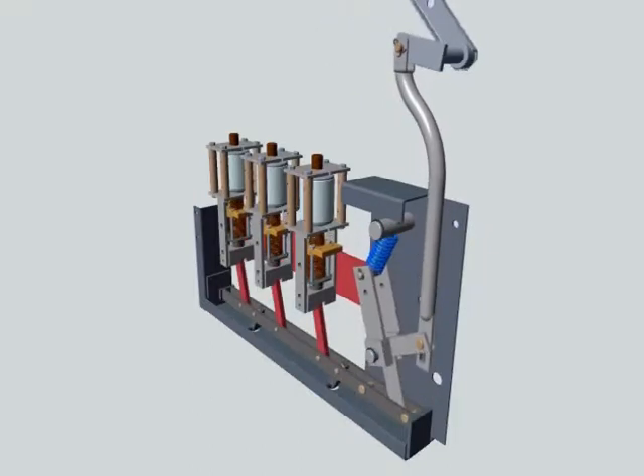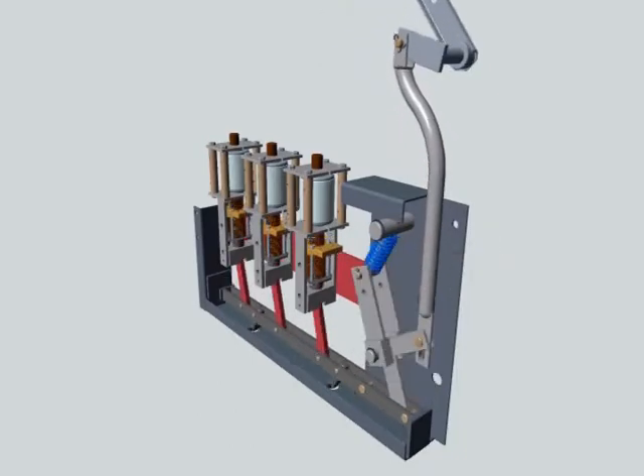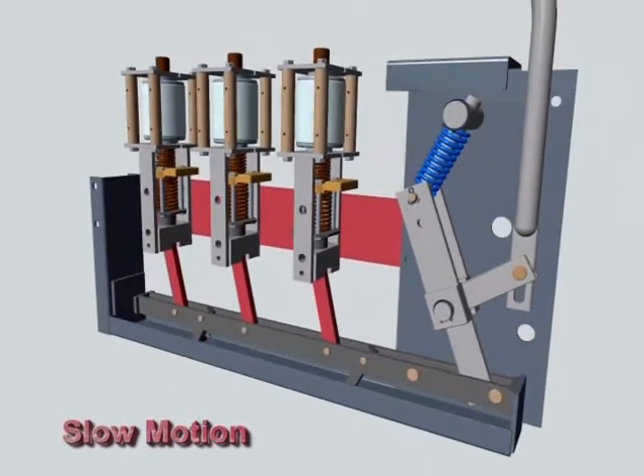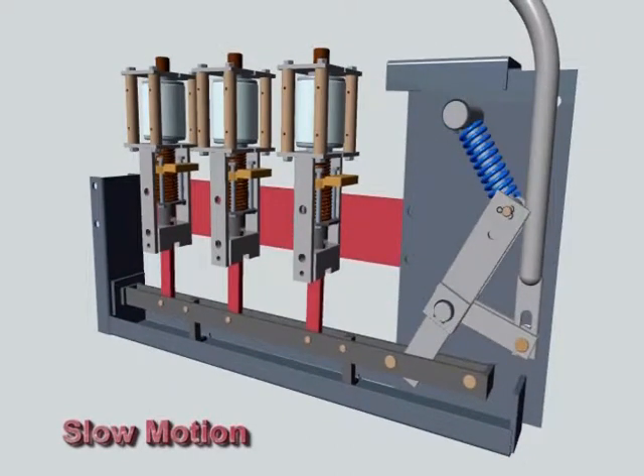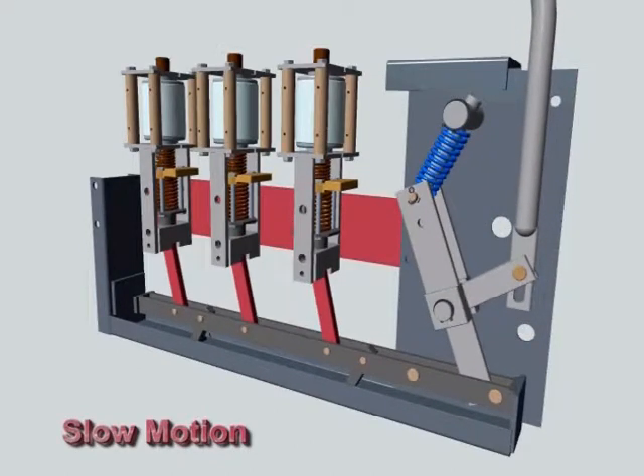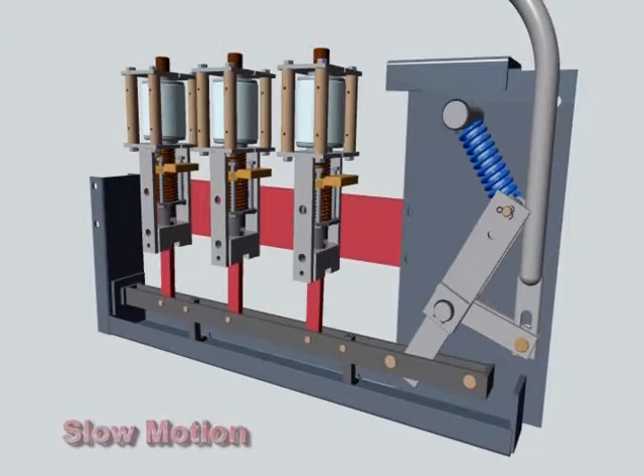A powerful die-spring-driven toggle moves the switch position bar between two welded steel stops. On the closing stroke, the switch position bar moves up on its two pivoting support legs, driving the contacts to the closed position, and moves down during the opening stroke to pull the contacts open.